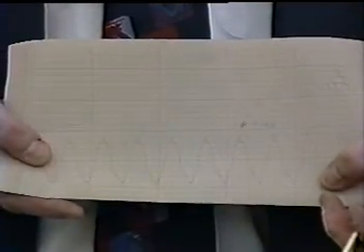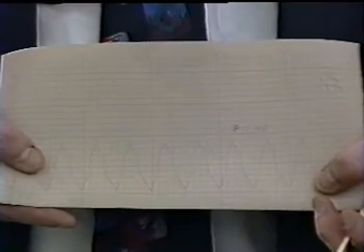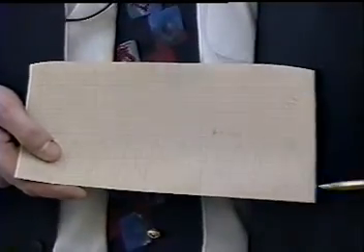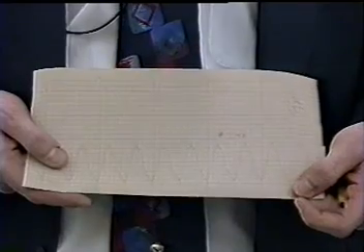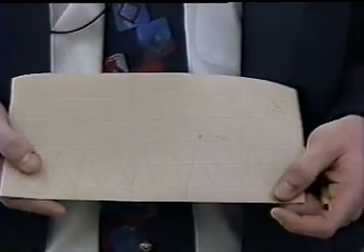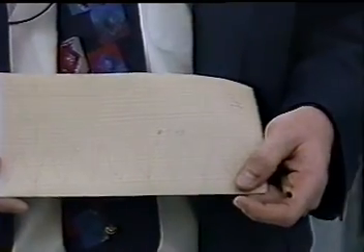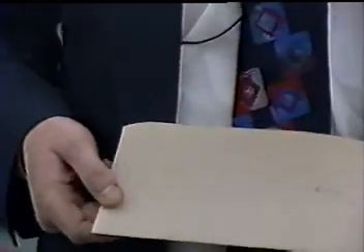For this particular test configuration, we're seeing 815 microstrain of damage. Microstrain is a measurement of how much damage is being done to the cable, and right now we are exceeding the endurance limit, and if we keep galloping for long periods of time, failure would occur. Now in the laboratory, we can gallop a span such as this for approximately 10 to 15 hours without failing the cable. But if we would go longer, it would fail.